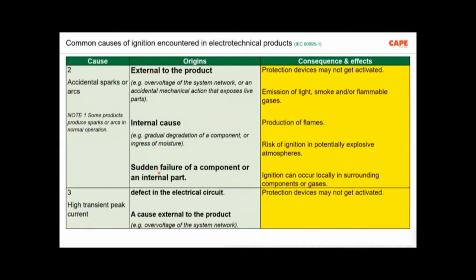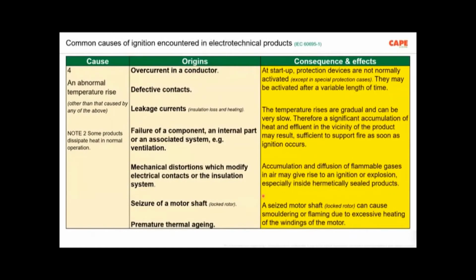Then internal causes, sudden failure of components; the consequences are written here. Protective devices may not get activated. That is always the first point of the effect. If the protective devices are not getting activated, or if the MCB didn't trip, of course we will be in trouble. The third problem is high transient peak current due to some kind of switching action, due to lightning, due to starting of a motor, due to switching of a long array of tube lights, and so on. So these also create some insulation failure where the protective device should trip and work and protect your installation.